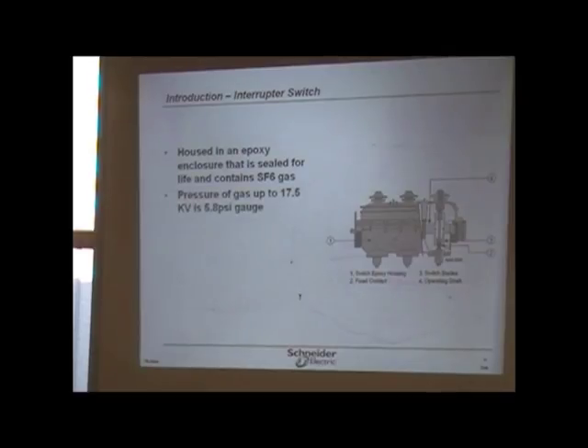I told you that Siemens has a switch similar to this that has SF6 gas in it. And like I said, this was at Cottage Hospital in California, where they said that they had to recharge it. Well, the Square D unit is sealed for life. So if this ever escapes, you're going to know that when you do your high pot, because then it's going to break down. You're not going to be able to get up to that, more or less a general rule of thumb, 2.5 times. And the high potting values we found over here when we did the switch, remember? Yeah. Okay, the same thing.